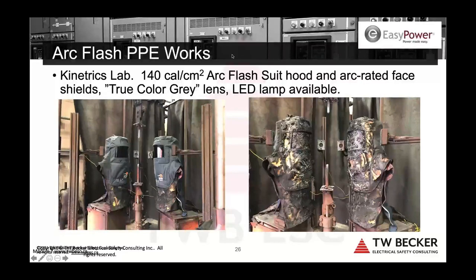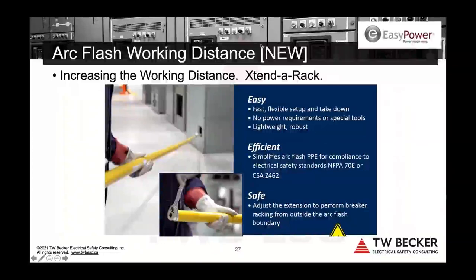Now, this is a very cool thing, too, that relates to arc flash. I just found out about this product last week. It is brand new. It's a Canadian product. It's called Xtend-a-Rack. So if you're doing the calculations, working distance, right? Default working distance in 1584: 18 inches for low voltage, 24 for low voltage switchgear, 36 inches for high voltage switchgear and MCCs. Now, this is a 17-foot telescoping hot stick adapted into a racking tool.